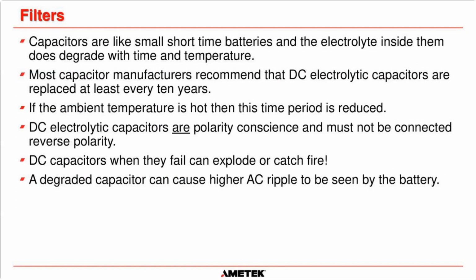Capacitors are like short-term batteries, and the electrolyte inside them degrades over time and temperature. Most capacitor manufacturers recommend DC electrolytic capacitors be replaced every 10 years. If the ambient temperature is hotter, that time period is reduced, quite drastically. So try to make sure your capacitors are kept in a room that's air conditioned, to prolong their lifespan.